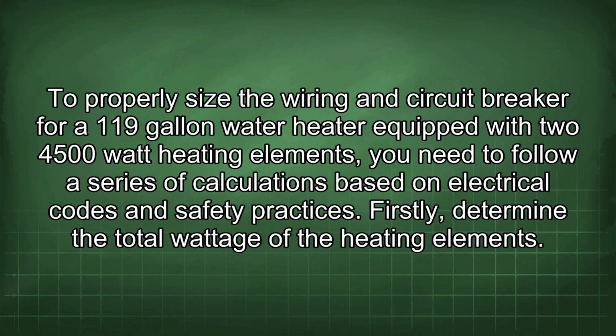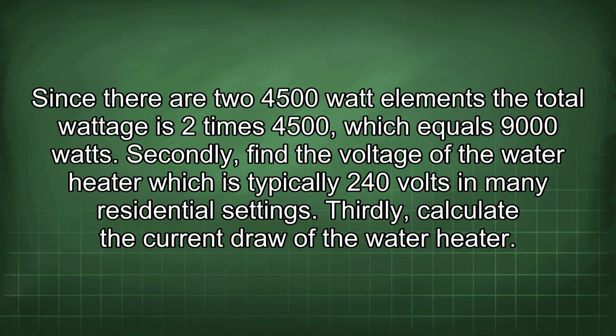To properly size the wiring and circuit breaker for a 119-gallon water heater equipped with two 4,500-watt heating elements, you need to follow a series of calculations based on electrical codes and safety practices. Firstly, determine the total wattage of the heating elements. Since there are two 4,500-watt elements, the total wattage is 2 times 4,500, which equals 9,000 watts.